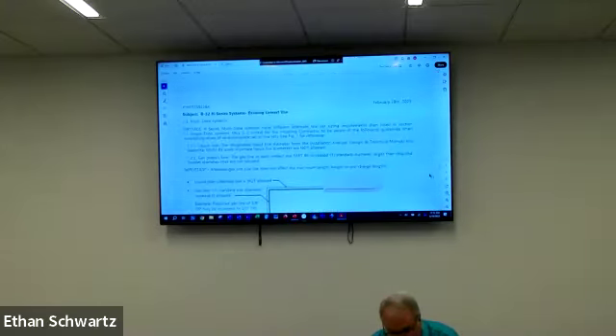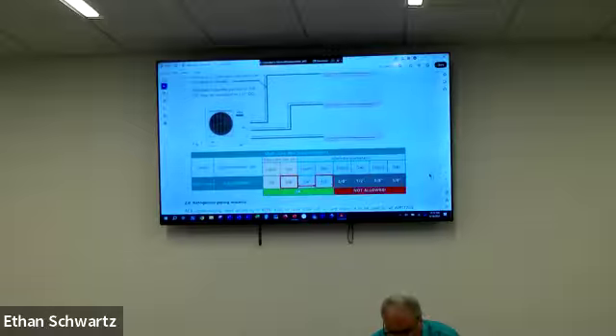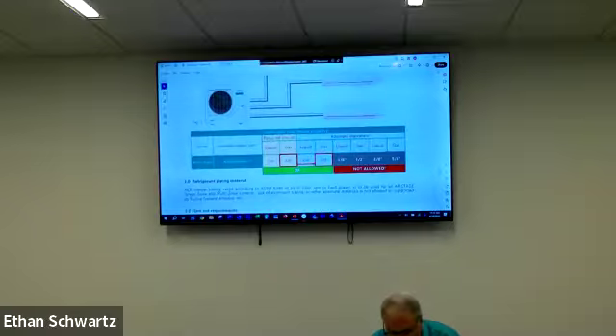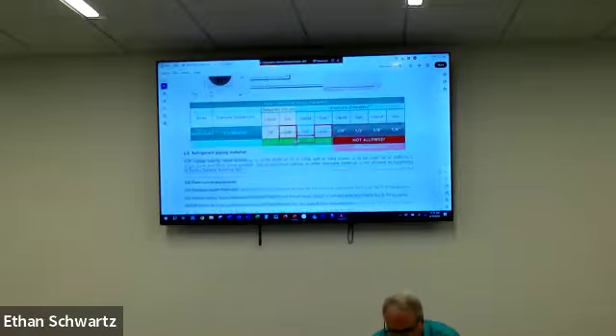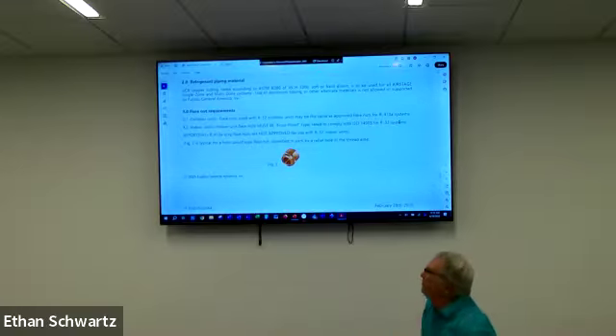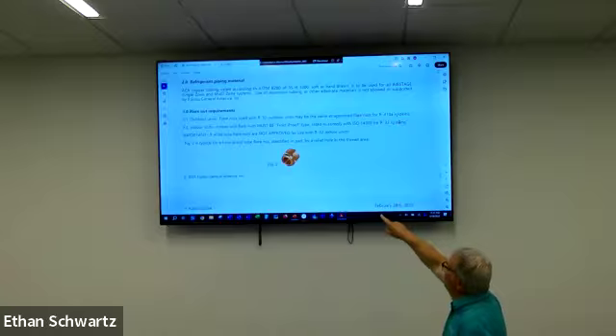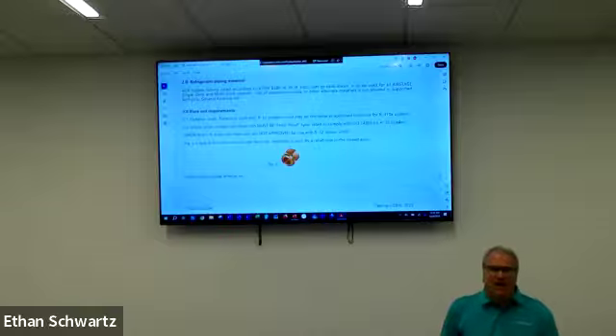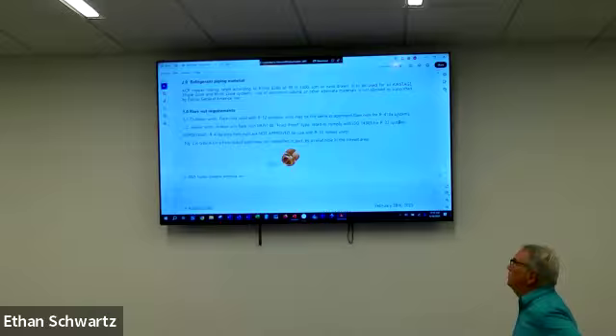Now here we're getting into the multi-zone systems. Some of those may come up, and some things are not allowed, so you're just going to have to look at that. And this is new for R32. What's allowed for R32 may be the same, but we need these frost-proof types. Have you heard that or seen that coming out? So that's what's in here, the ones that have those holes there.